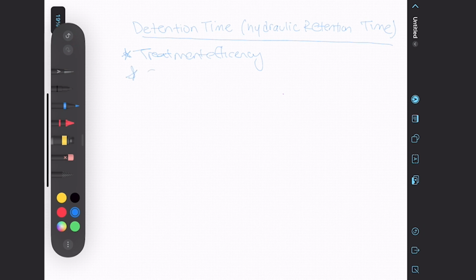Another place is chemical reactions. Many treatment processes involve chemical reactions, such as chlorination for disinfection or coagulation for removing particles, so we're going to be looking at detention time. And we need to look at this number to understand and ensure what the necessary time is for these reactions to occur, to ensure that the reactions are complete and achieve the desired treatment objectives. So detention time is equal to the volume over flow. Okay, let's do a practice problem.